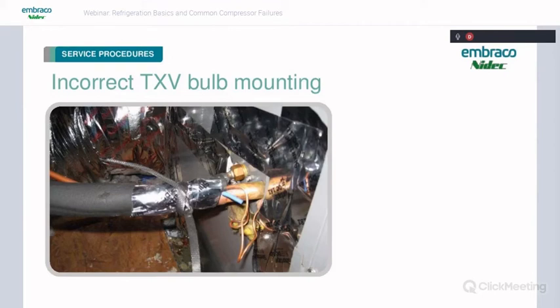And in a low load condition, if you have a low load condition outside, but you're still a little warm in this attic or wherever this room is, you're going to start feeding too much refrigerant to that evaporator and not have enough heat load to evaporate it. And guess what? You're going to get liquid refrigerant returning to the compressor. So this is why it's very important to mount those bulbs very securely and insulate them well. If you do that, TXV valves are very reliable and operate very well.